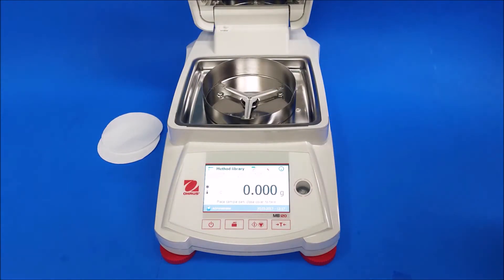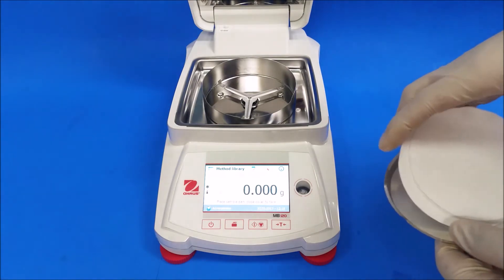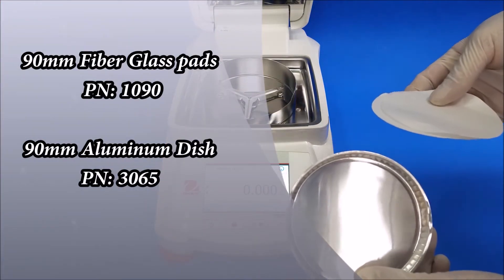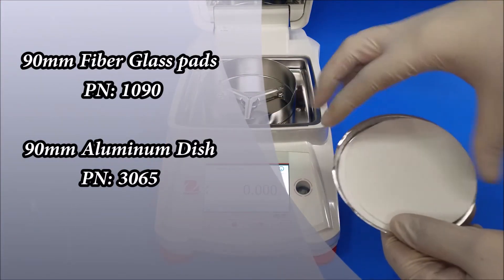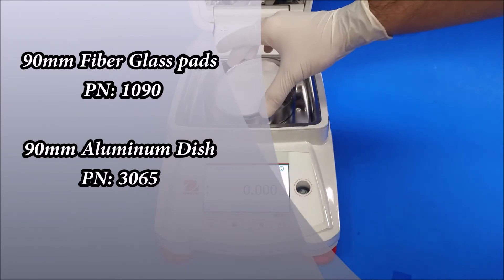You don't need to do much on this unit since it tares itself and starts itself. So what you're going to do first, I'm just demonstrating, I'm going to put my aluminum dish and two pads.